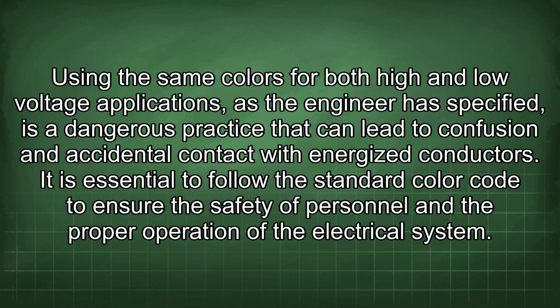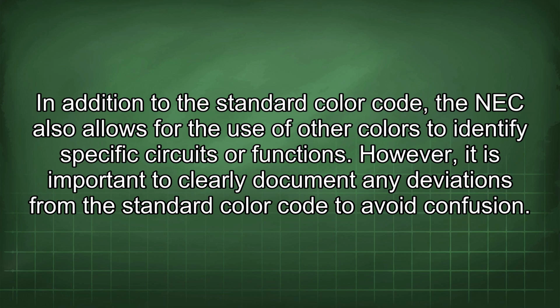Using the same colors for both high and low voltage applications, as the engineer has specified, is a dangerous practice that can lead to confusion and accidental contact with energized conductors. It is essential to follow the standard color code to ensure the safety of personnel and the proper operation of the electrical system. In addition to the standard color code, the NEC also allows for the use of other colors to identify specific circuits or functions. However, it is important to clearly document any deviations from the standard color code to avoid confusion.